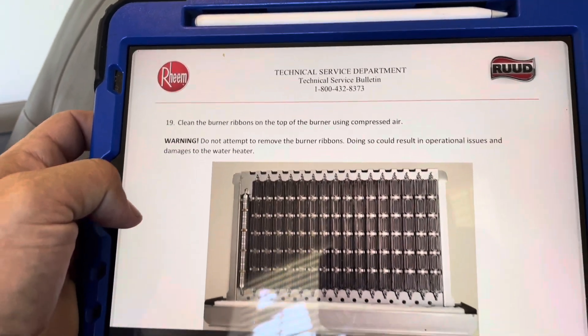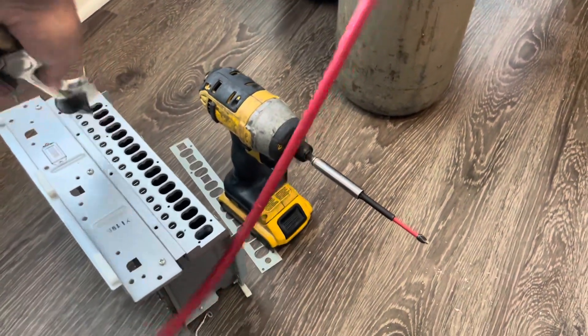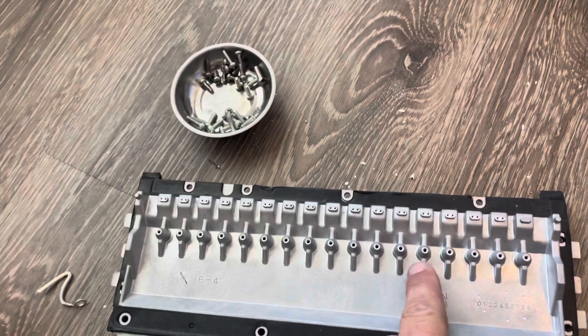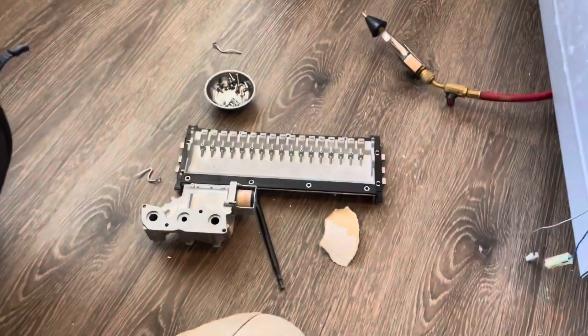Clean the burner ribbons on top of the burner using an air compressor. I'm going to use nitrogen and just blow it all out. We got our nitrogen hooked up and we're blowing out anything that's in there - doing the same thing in the heat exchanger too. I actually had to call Rheem because a couple of the orifices had no flow through them and I didn't know if that was by design or a really solid clog. They said it's by design - these end five orifices are supposed to have no flow through, so we're good.